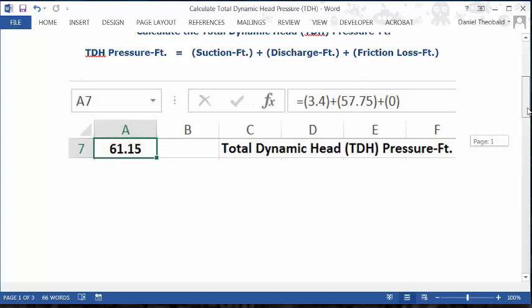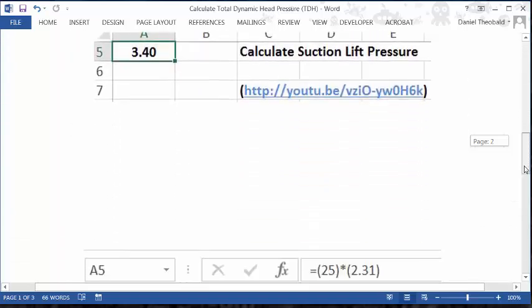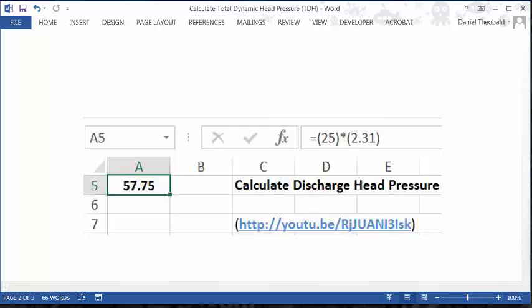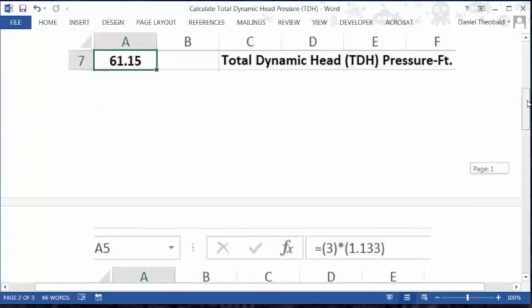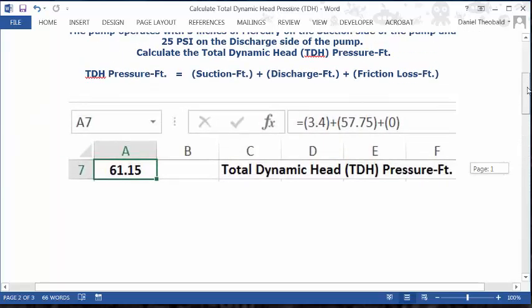Now let's look at how we calculate discharge head pressure — there's a separate standalone video for that. In that one we use 25 PSI and multiply it by the standard conversion factor from PSI to feet of head pressure, which is 2.31. That gives us our answer of 57.75 feet of head pressure. The URL for further explanation is shown, and the 57.75 is inserted into the formula.